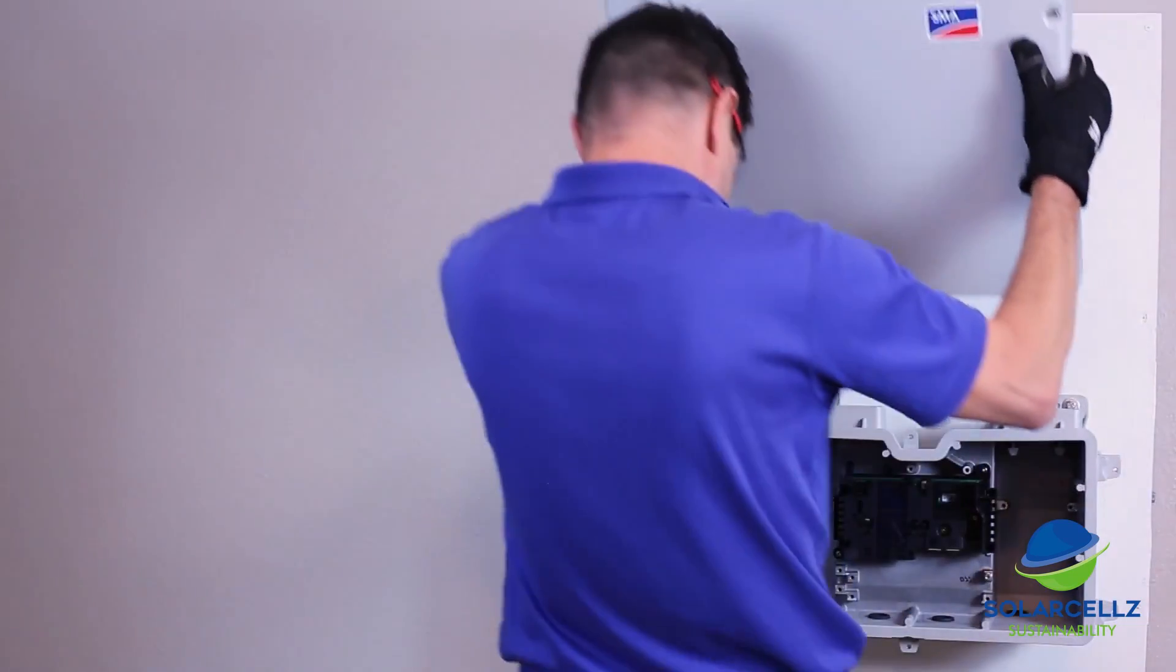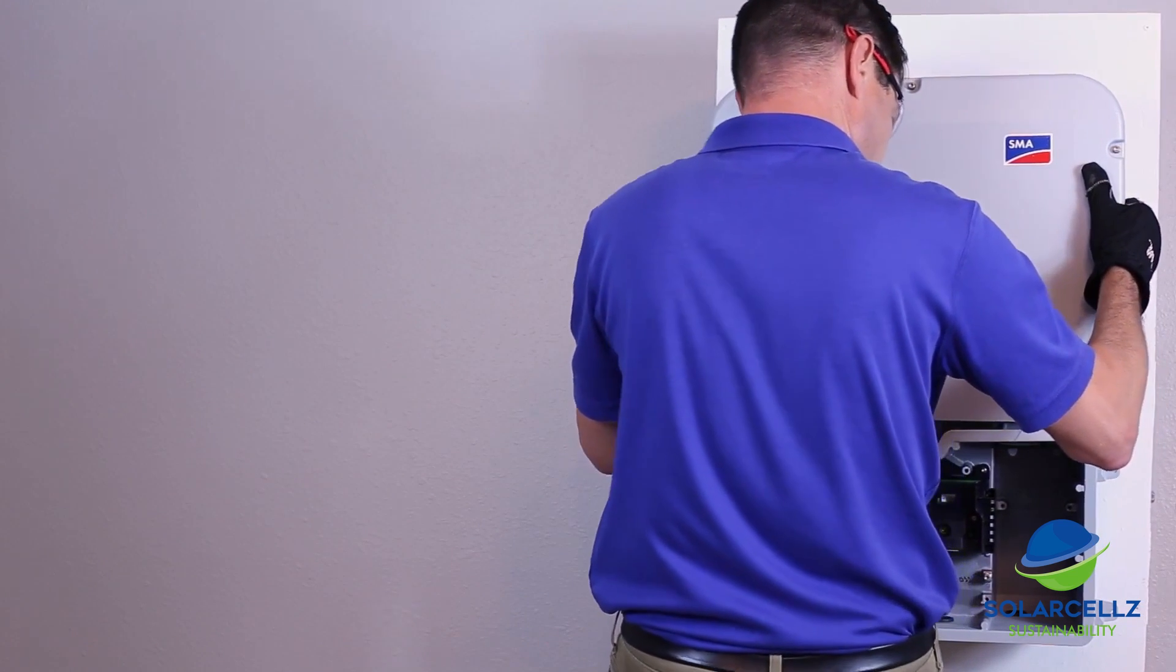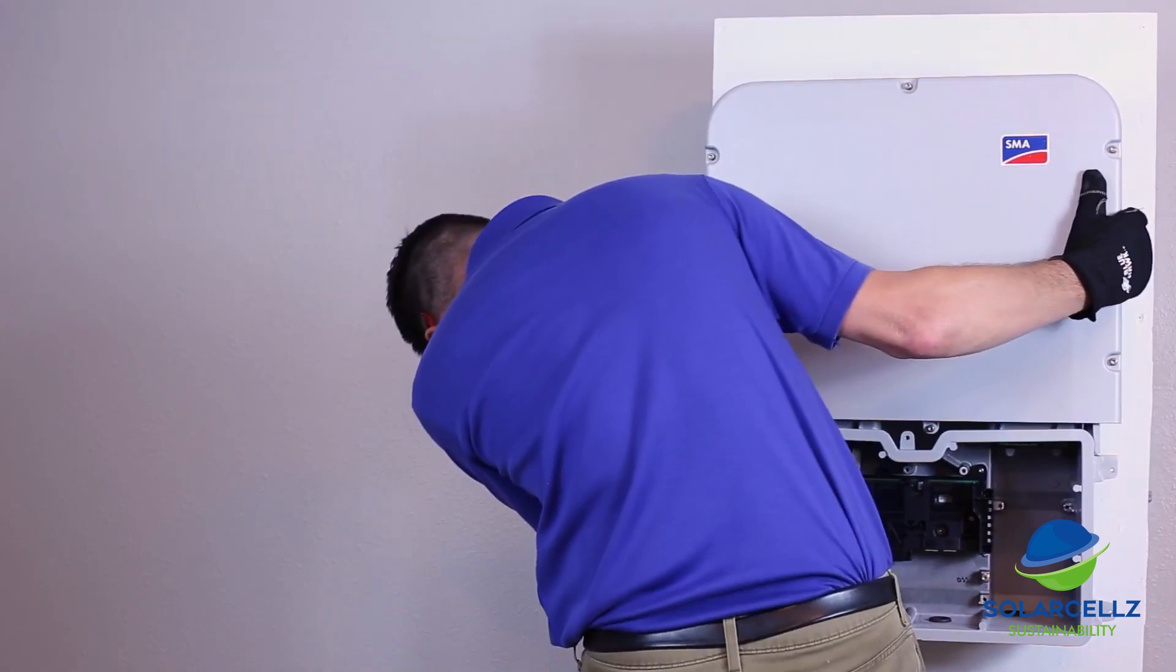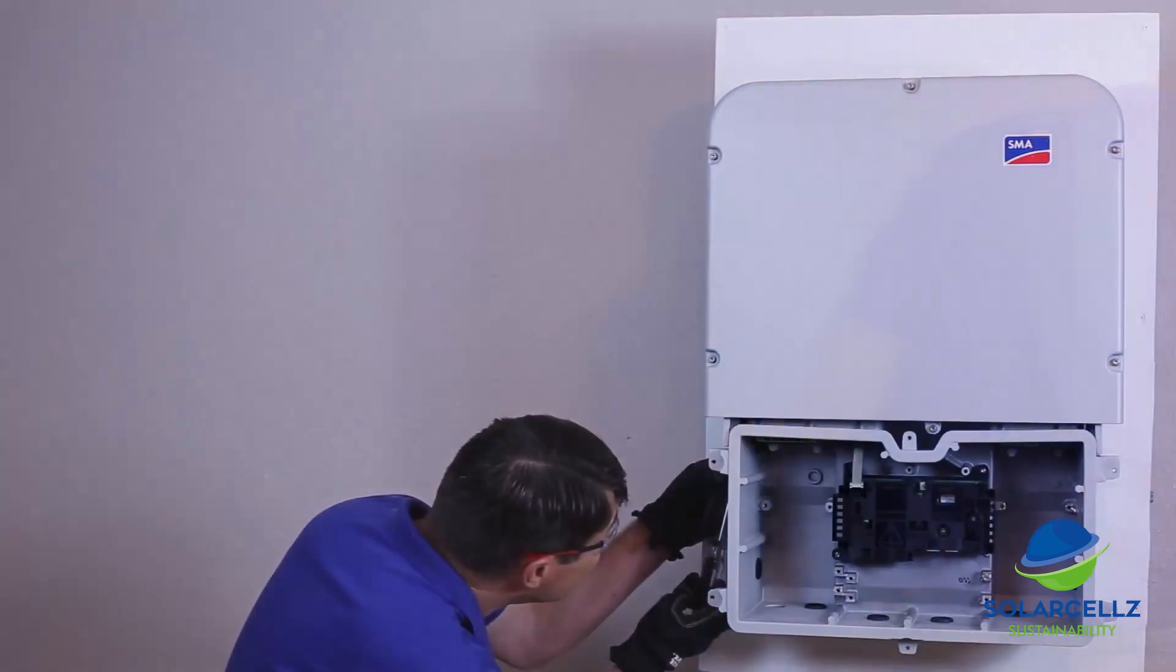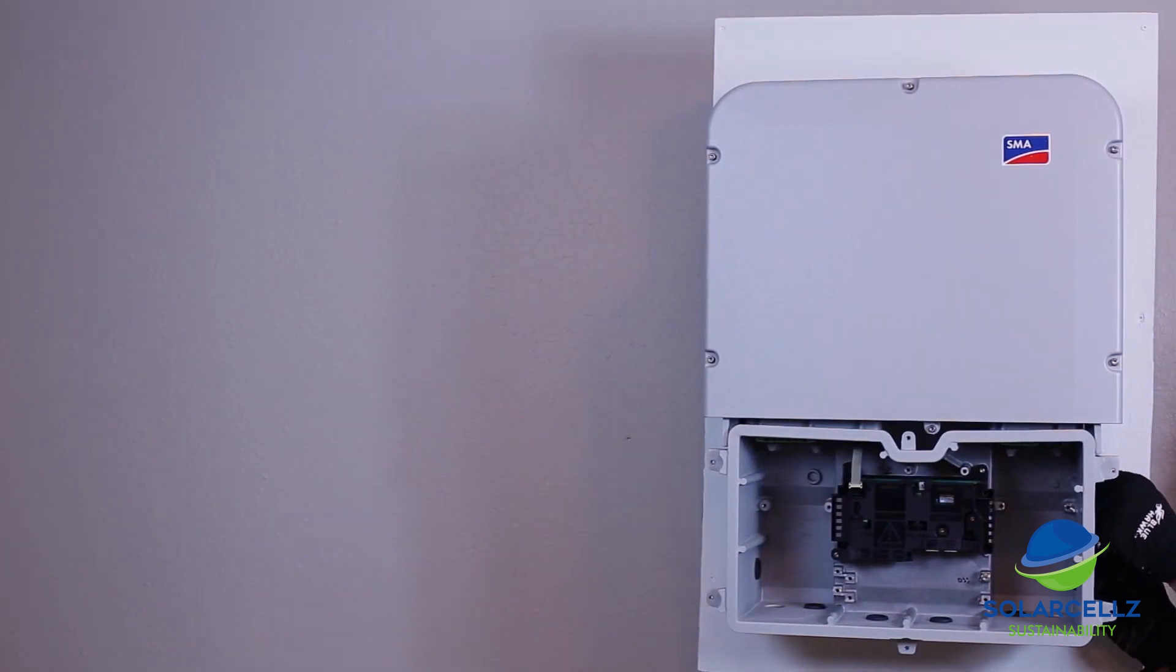Now the power unit can be placed on top of the connection unit and reattached. Ensure the ribbon cable is safely inserted into the connection unit and not pinched or damaged. Secure the power unit to the connection unit by reattaching the four Torx 25 screws and tightening to 53 inch-pounds.